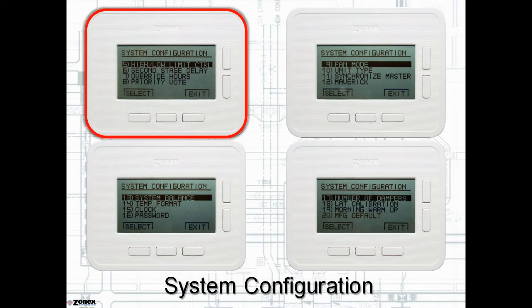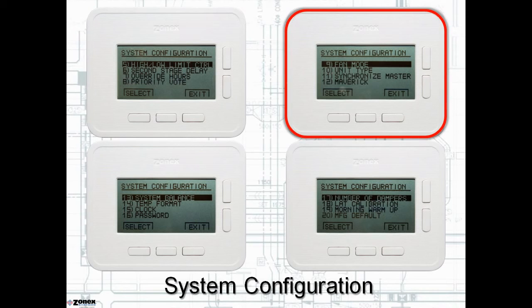System defaults provide one vote for each thermostat. However, the installing contractor can skew the voting by giving a stat 1, 2, or 3 votes if required. If you want to delete a thermostat from the vote, a 0 option is also available on the priority vote menu. Fan modes and unit type are also selected from the monitor thermostat.